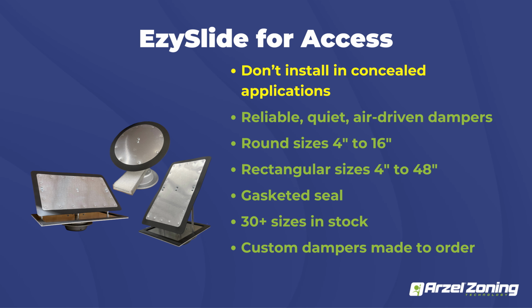Also, things to keep in mind with the EzySlide dampers, these do stick out of the bottom of your duct. So they're more used if you're not going to finish off a basement. If you've got a homeowner that's planning on finishing the basement and burying all their dampers, we do not recommend you bury our dampers or any dampers in general under drywall. If it's drop ceiling, you're more than welcome to do that. But if they're going to drywall, we have different dampers that we'll cover in a couple slides that are more geared for that kind of situation.